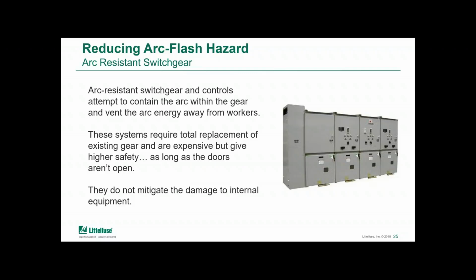Another form of arc flash mitigation that is certainly being discussed and is widely used in some applications is arc resistant switchgear. So this really acts as a permanent layer of extremely effective PPE and redirects the arc flash and the blast energy out away from the workers. You can see in the picture here a little bit of a vent in the top corner on the side. Now this gear can be expensive and can even be a little more expensive if you factor in the retrofitting of the building to maybe vent that arc.